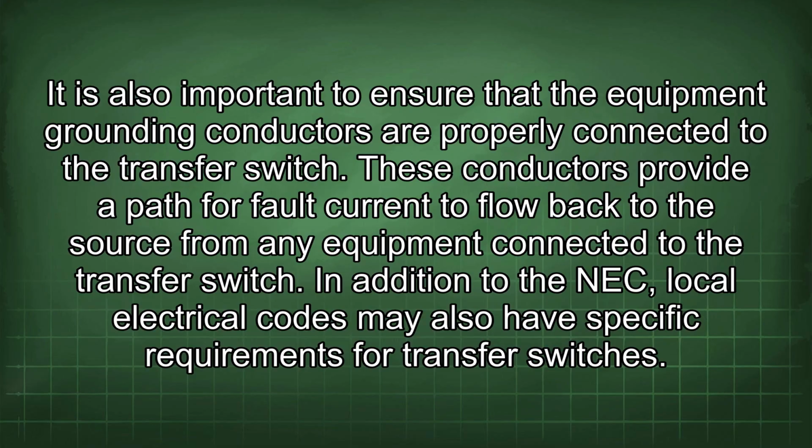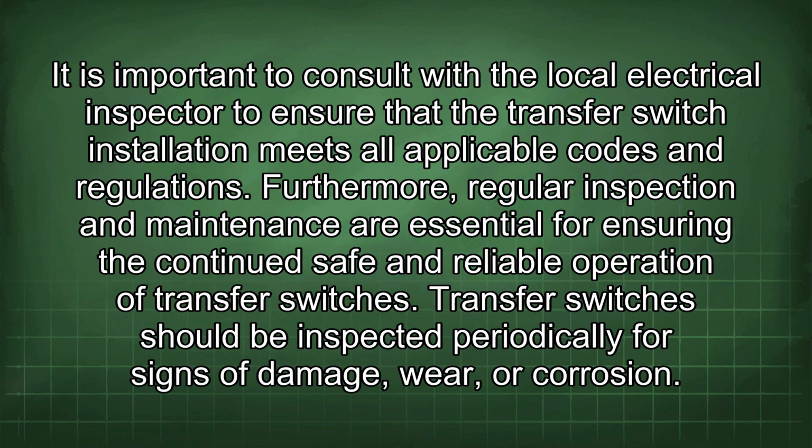It is also important to ensure that the equipment grounding conductors are properly connected to the transfer switch. These conductors provide a path for fault current to flow back to the source from any equipment connected to the transfer switch. In addition to the NEC, local electrical codes may also have specific requirements for transfer switches.